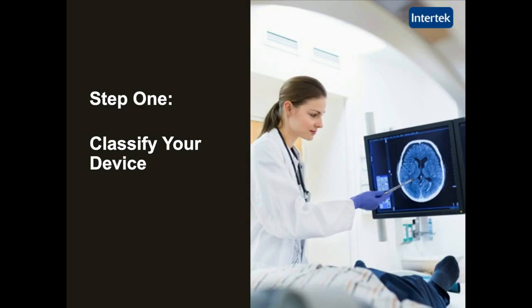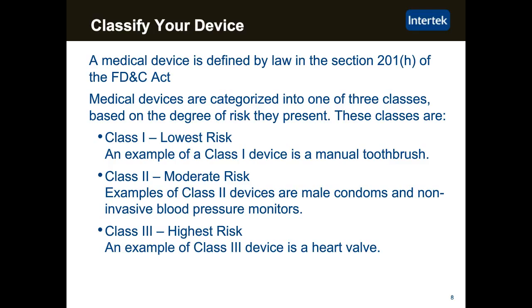So step 1, classifying your device. A medical device is defined by law in the FD&C Act. Medical devices are categorized in the U.S. into one of 3 classes, and that's based on the risk that they present to either the patient or the user. These classes are Class 1, which is the lowest risk level, and an example of a Class 1 device is a manual toothbrush. Then you move up to Class 2, and these are moderate risk devices. Examples of a Class 2 device may be a male condom, or it could be a non-invasive blood pressure monitor. Class 3 is the highest risk class of device, and an example of a Class 3 device might be an implantable heart valve.